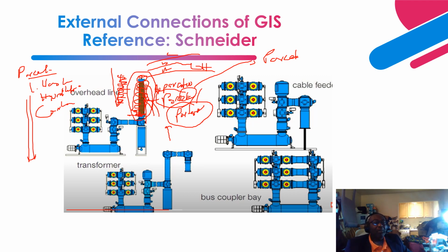You have an external element of the weather, moisture, intruding into the SF6. Remember, the SF6 is acting as an insulating medium. In here, right, it is going to intrude and basically degrade the integrity of the insulation medium. And you can have all sort of basically PD activity, etc., right, inside this medium. So that is one of the disadvantages or the drawbacks of the porcelain insulation medium.